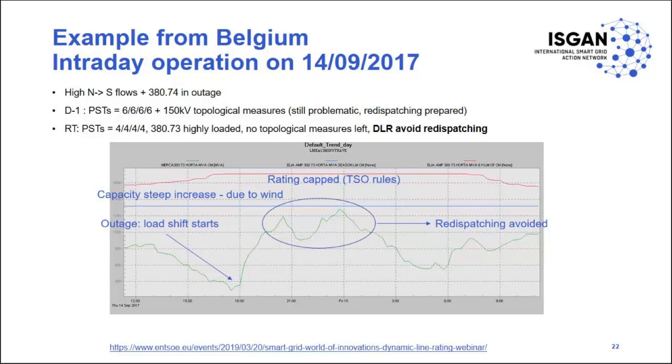However, one of the backbone transmission lines was out of service due to maintenance work. It was being upgraded to a line with high capacity, so it couldn't be brought back into service at short notice. At this stage, this meant that during those peak hours, it was highly likely that the resulting power flows would be too high to ensure an N-1 security of the grid.